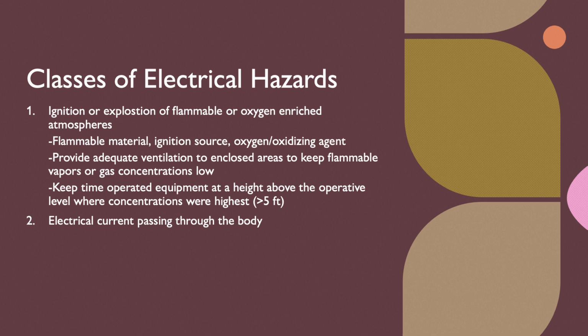Ignition risk exists because of supplementary oxygen used for respiratory patients. A frayed wire or damaged equipment can leak current, and in a closed room the oxygen content can become so great that a spark could cause an explosion and a huge fire. There are three basic requirements for ignition: a flammable material, like blankets, an ignition source like a spark, and oxygen, which is already in the air, if not more so from the oxygen concentrator.